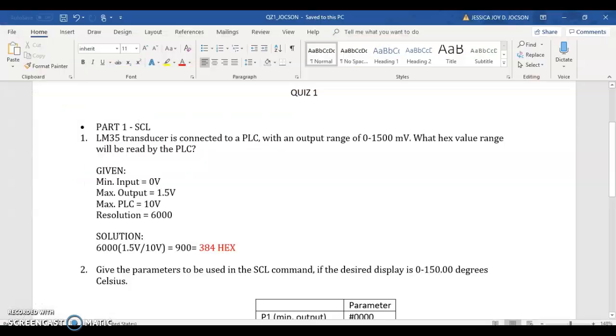The problem is an LM35 transducer is connected to a PLC. What is the LM35 transducer? It's simply a temperature sensor, whose analog voltage output is proportional to the temperature, with an output voltage range of 0 to 1.5 volts. In reality, the maximum output range of the PLC is 10 volts, and the resolution is 6000.